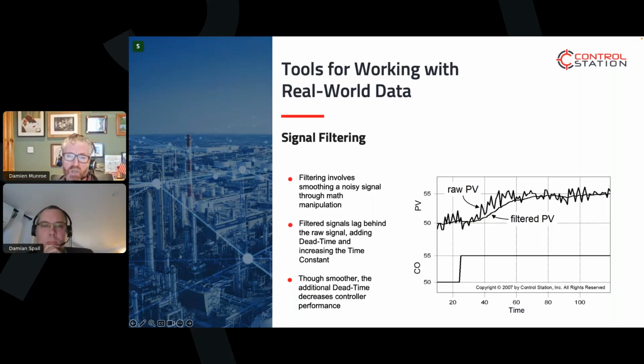But really, where filtering kicks in is time constant and dead time. If you look at the difference between the raw PV, almost where the arrow is pointing, and a straight line across to where it hits the filtered PV, that's how much time constant we've added. It's probably in excess of 50%.